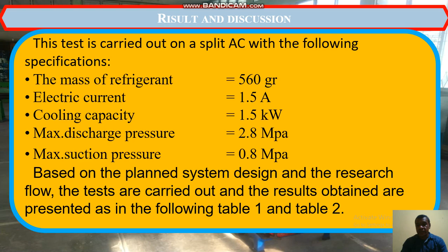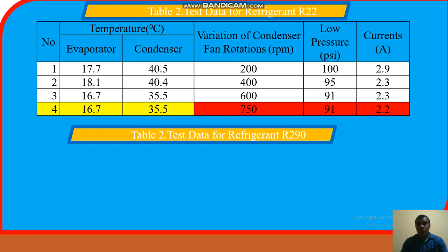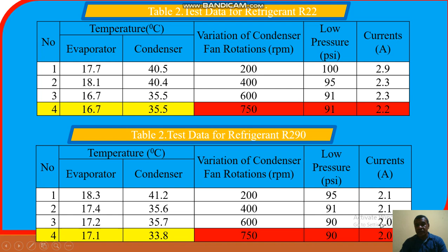Table 1 is the data we got for refrigerant R22. This is the result, and then table 2 is data for the hydrocarbon refrigerant, or the other name is refrigerant R290, sorry, R290. We look closer at the result. When the RPM is 750, the same fan speed, we get different pressure. At refrigerant R22 we get 91 psi, and the hydrocarbon is 90. Likewise, the current consumption in R22 is 2.2, and the hydrocarbon is 2.0.